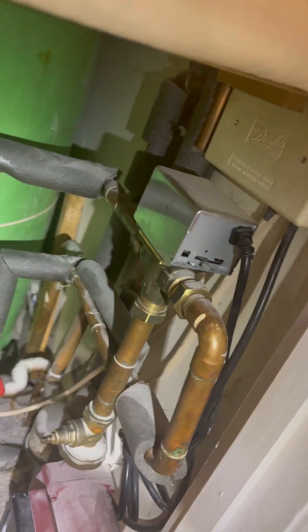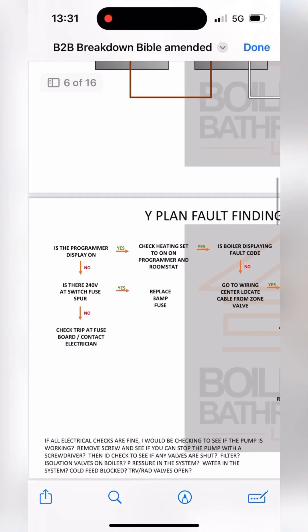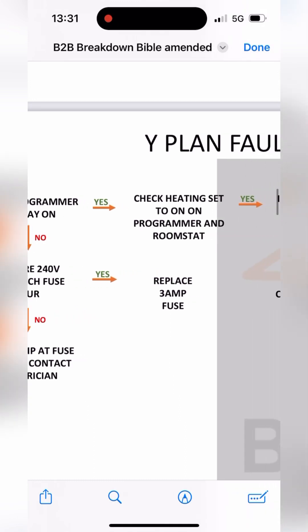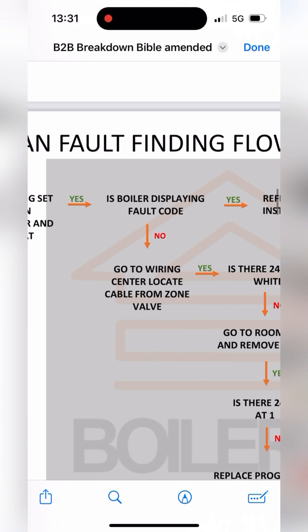Go upstairs - Y plan system. Whip out the breakdown bible, go down to Y plan fault finding flow chart. No heating: is the programmer on? Yeah. Programmer's set to heating, room stat's up. Is the boiler displaying a fault code? No it isn't.